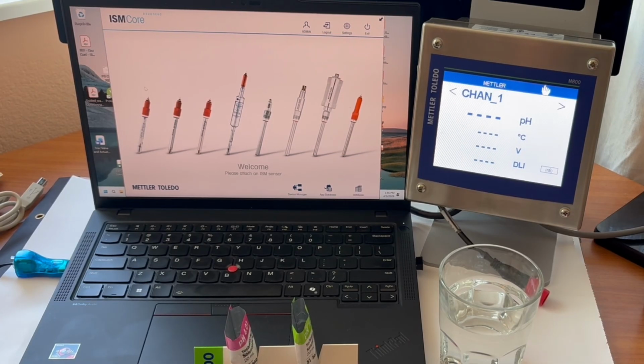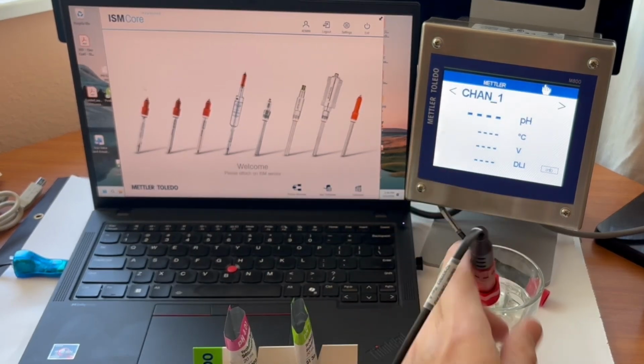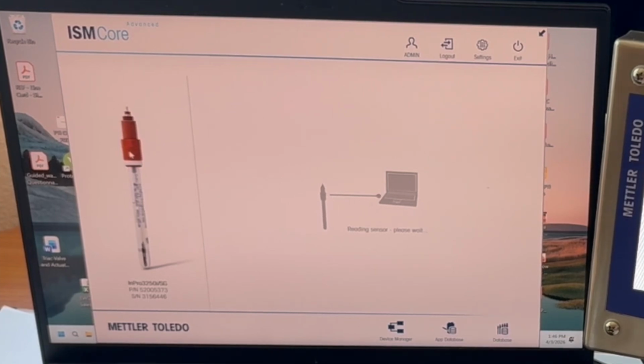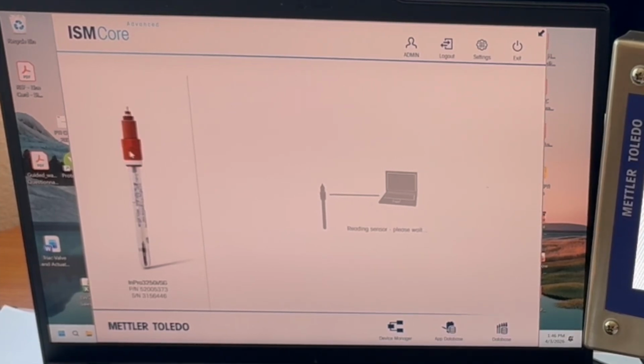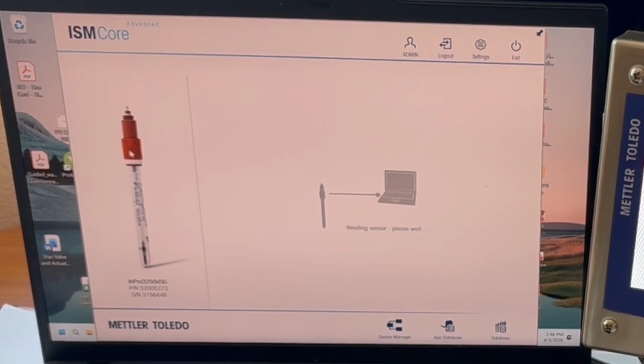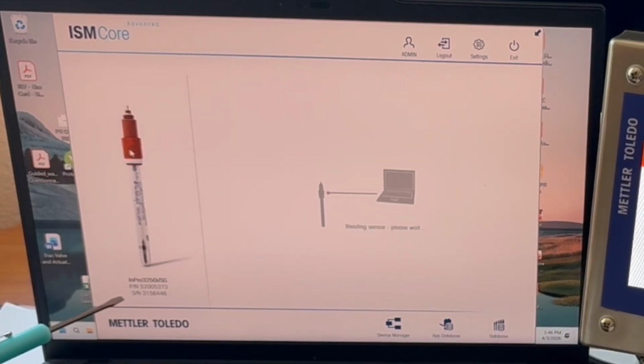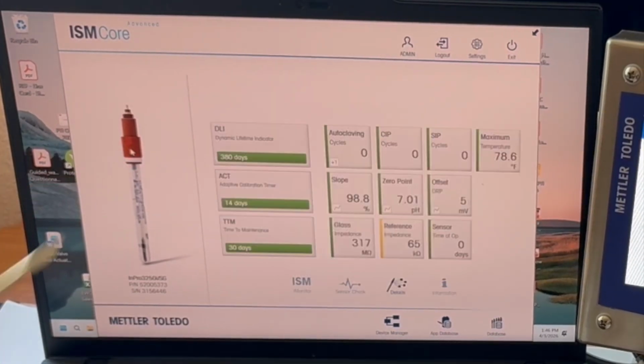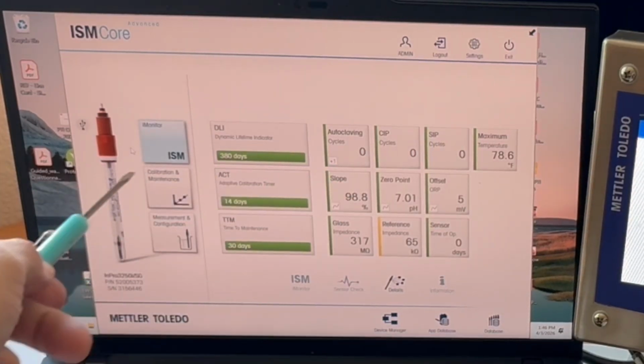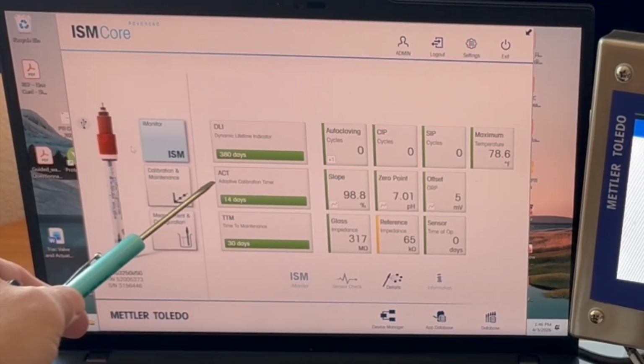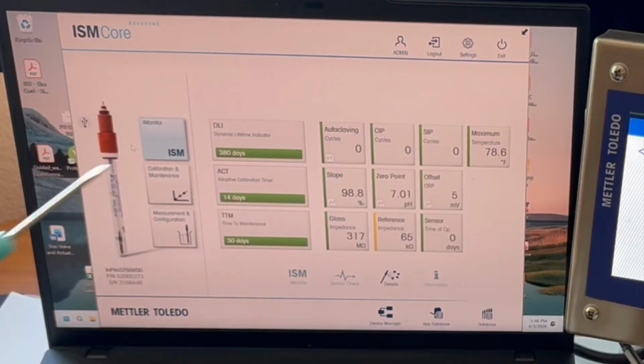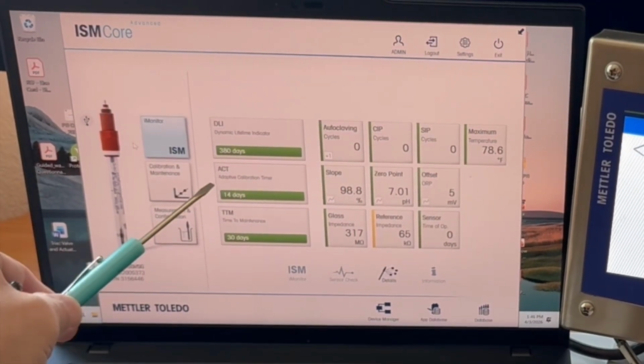When I hook up a sensor, that's simple. Put that probe into some water. Like this transmitter, the program immediately recognizes there's a sensor attached. It's showing us the part number and serial number for the sensor while it reads the data off the sensor, and then it populates this field. Literally what we have is color indications, all the details for this sensor.